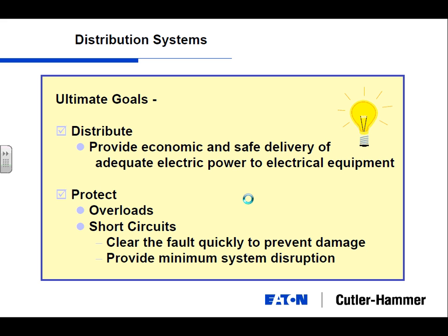And just by thinking about the overload and the short circuit, which one has the tendency to be more dangerous for the facility or the people working on the equipment? Overload or short circuit? Short circuit. A short circuit can be a very dangerous situation. And when we talk about danger in electrical distribution, you'll hear the words arc flash energy. I don't know if you've talked about that yet, but arc flash energy came into the code, and the awareness of it became more prevalent in the last 5 years.